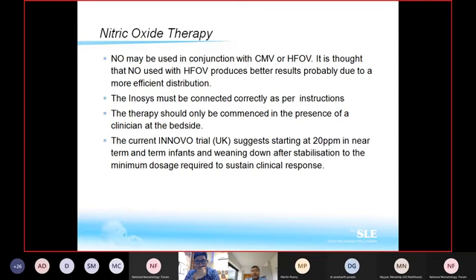You need to ensure that the scavenging filters are being used, and that when you are removing this gas, it's being done properly. Also, you need to ensure that the gas is sampled at the patient connector, so that the patient is getting the right proportion of NO and NO2, and that's being monitored in the main equipment.